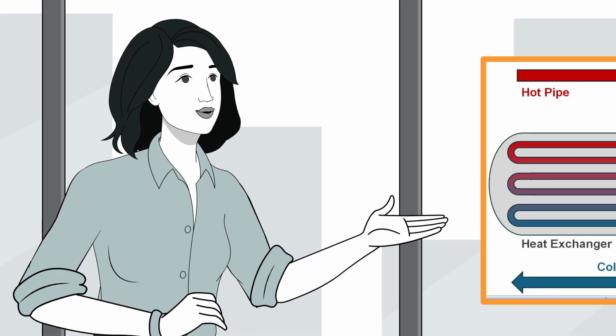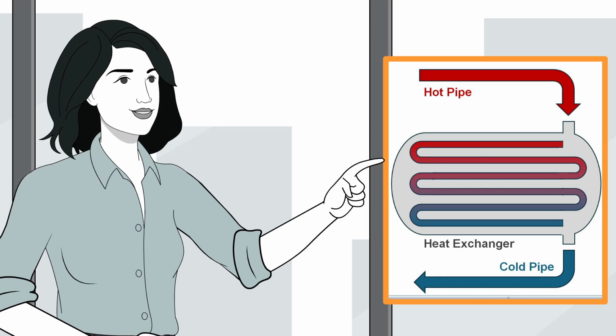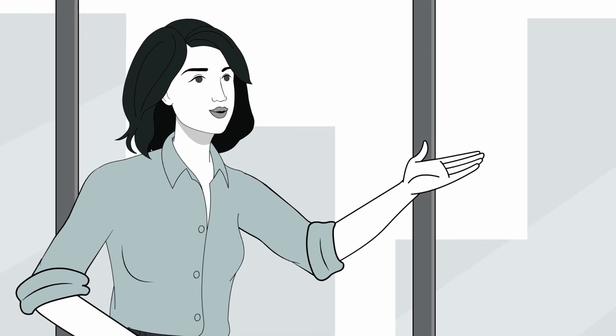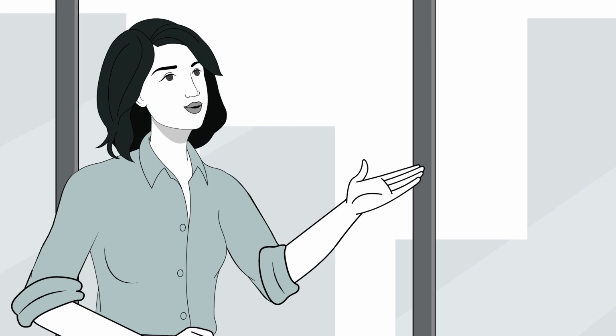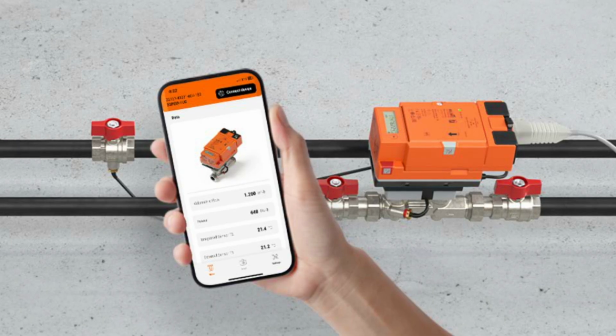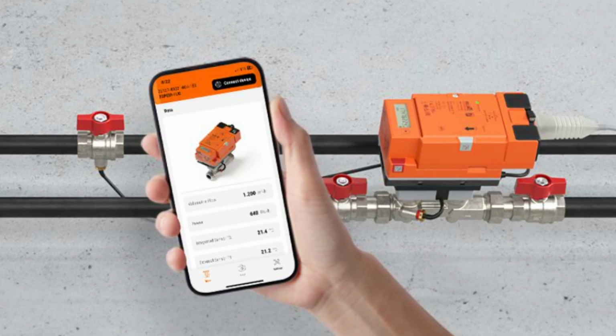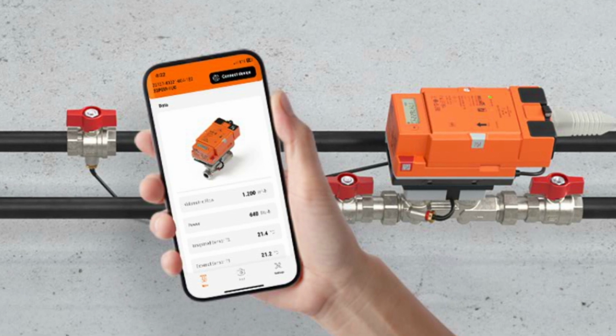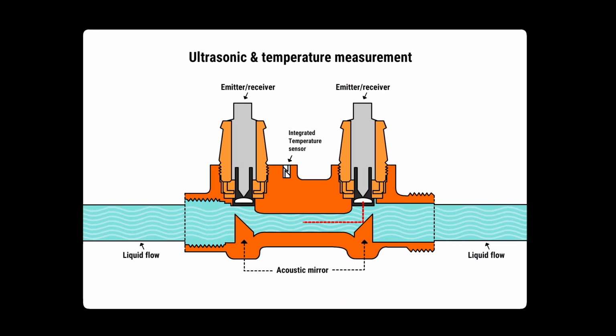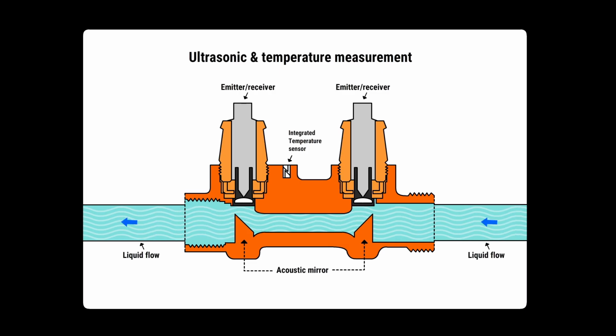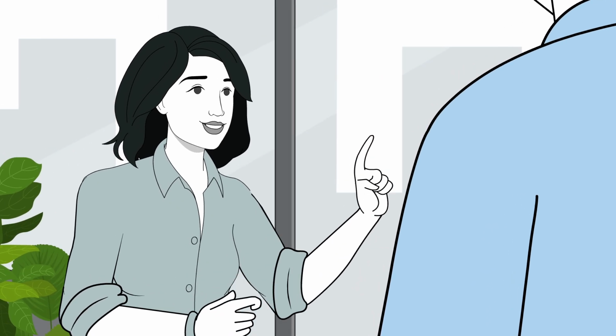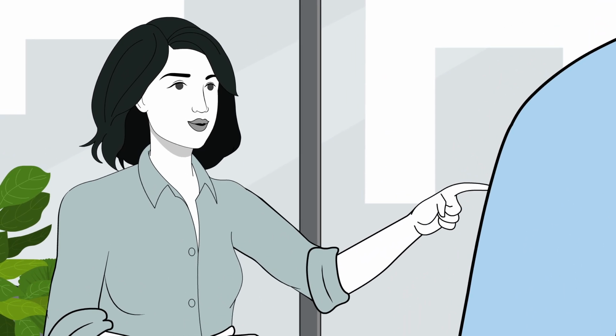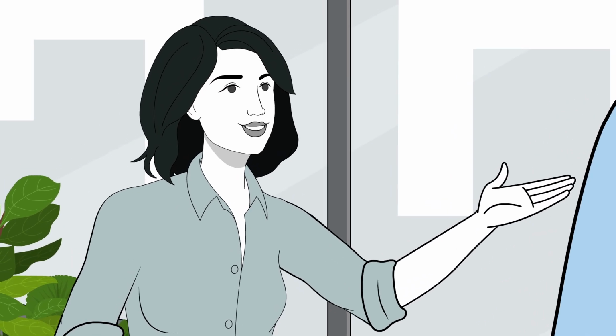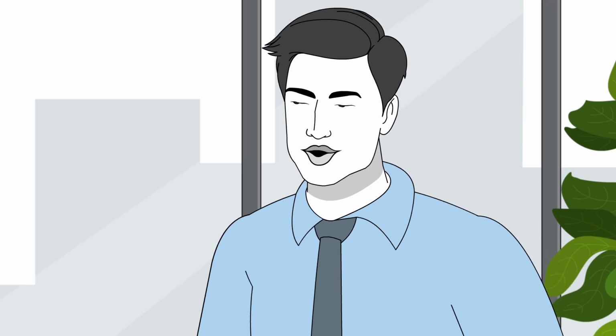A thermal system involves a hot pipe, a heat exchanger, and a cold pipe. Belimo's thermal energy meters measure not only the flow rate going through the system, but also two temperature readings, one from the hot pipe and one from the cold pipe. The meter's flow sensor uses ultrasonic waves, which bounce back and forth in the pipe, which accurately measure the flow rate of the water traveling through. Using the flow rate and the temperature readings taken from either side of the heat exchanger, the meter can then calculate the system's energy. Wow, that's really clever.